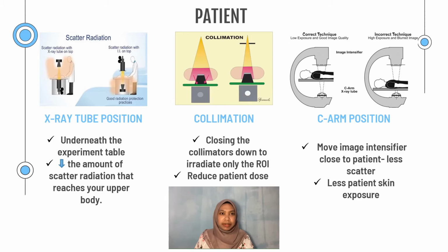Okay, this is the first part, safety of patients. Firstly, the X-ray tube needs to be positioned under the examination table. By positioning the X-ray tube below the patient, the amount of scattered radiation that reaches your upper body will decrease. As you can see in the picture, when the X-ray tube is put on top, the radiation will increase on the patient and the staff in charge. However, if we put it underneath the table, good radiation protection is practiced.